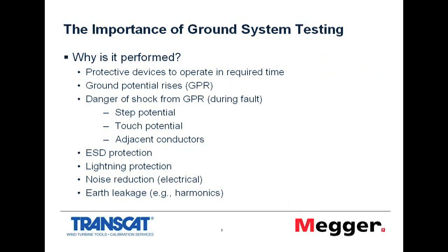Okay, the importance of ground system testing. Why is it performed? The connection to ground on many systems is a very important connection, and it's very important that the resistance of that connection is as low as possible. On a power supply system, if there is a fault, how fast the protective devices will operate will depend on how much current is flowing. If your connection to ground isn't low enough, then those protective devices may not operate in the time required and therefore not offer you the protection required.